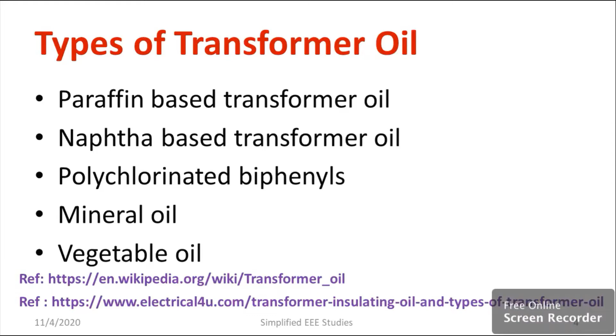What are the different properties of transformer oil? Let us look at electrical properties. It should have high dielectric strength - that is a desirable property. Similarly, it must have high specific resistance, and the dielectric dissipation factor should be as minimum as possible - it should be less. That means tan delta. You can measure dielectric dissipation factor in terms of tan delta, which should be as minimum as possible.